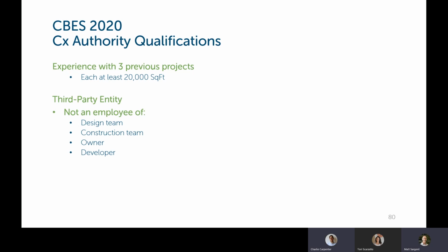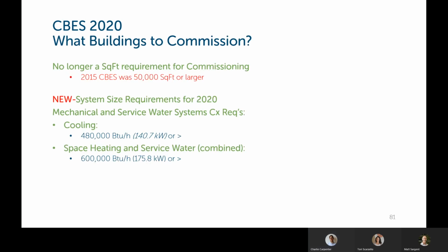Next slide. Is this a new provision, Charlie? I believe, yes, some of these have, or at least the experience part has been added. The third party is not a change. There are some more changes to this section of commissioning for when you know which buildings need to be commissioned or not. So the provision from the current code, the 2015 energy code, was any building 50,000 square feet or larger must be commissioned. That square footage requirement has been removed from this portion of the code, and instead it is mechanical heating and cooling size requirements that trigger whether commissioning is required.